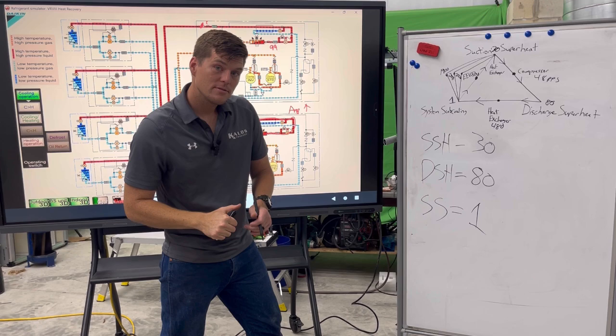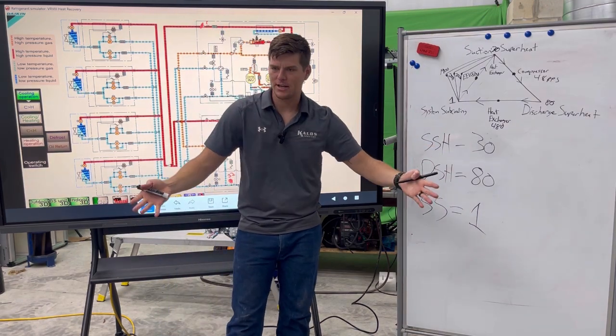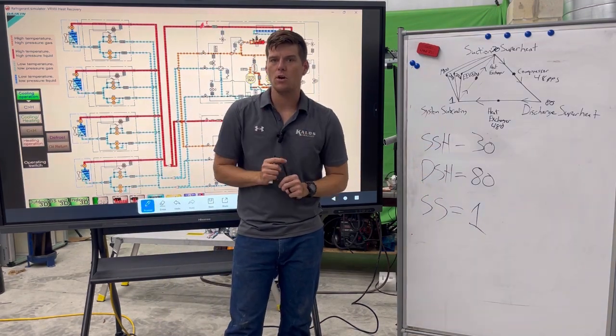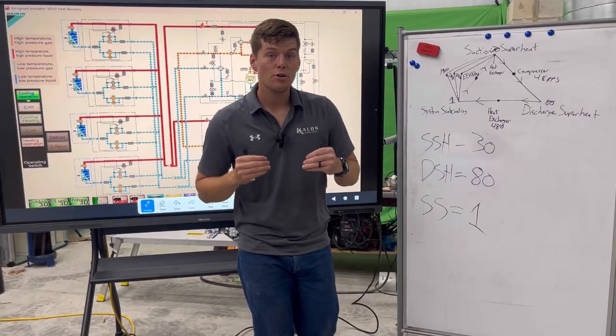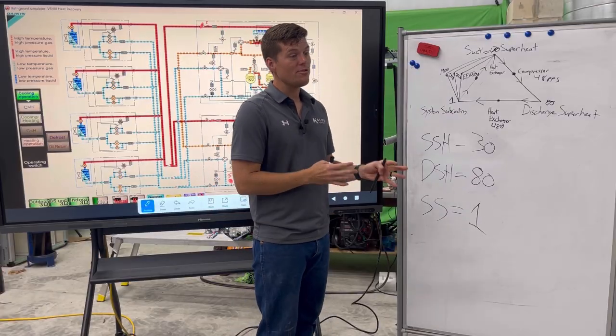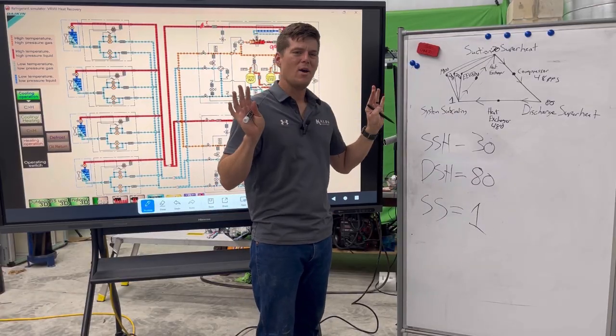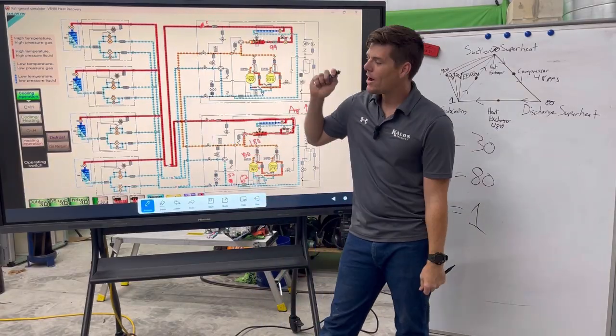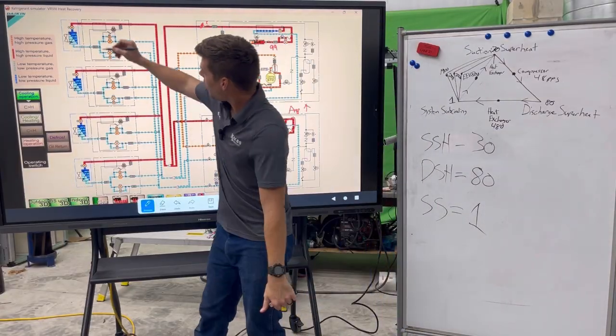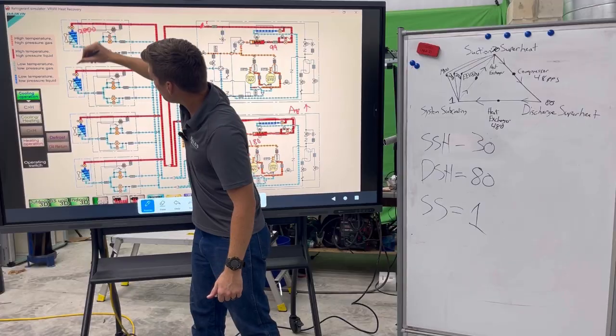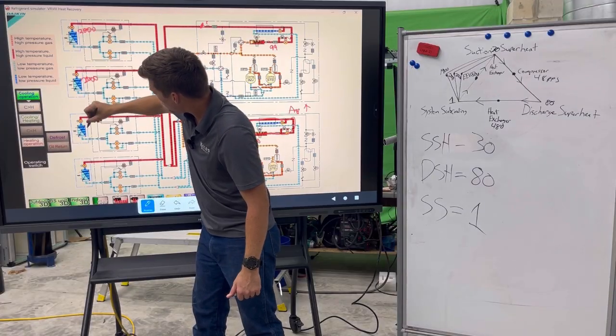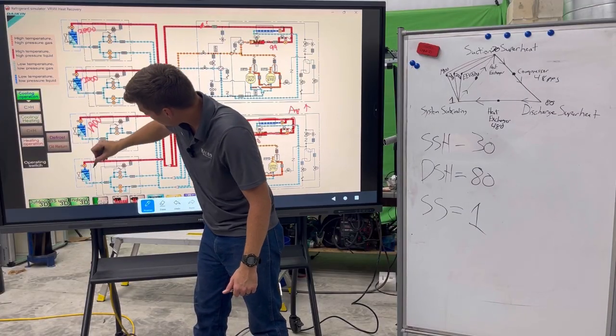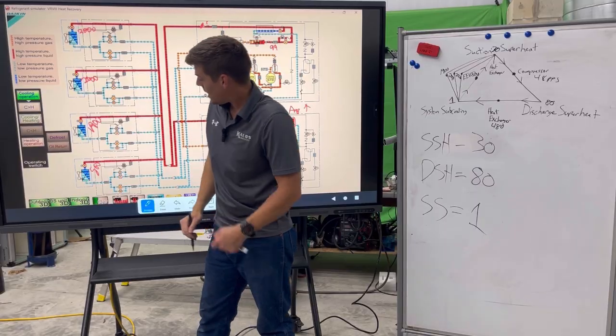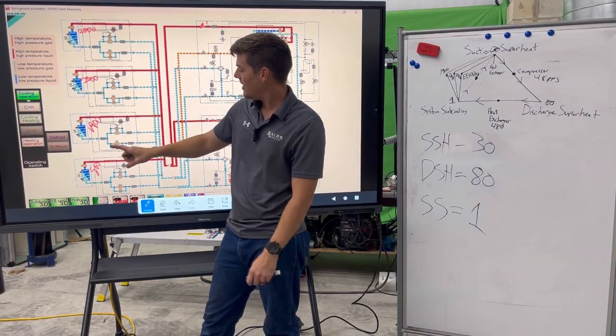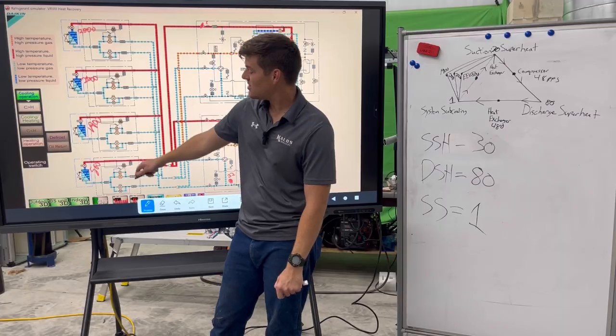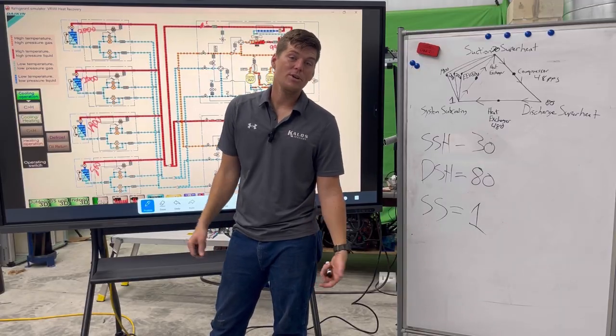Well, that's not good. Remember, the whole purpose of an electronic expansion valve is to do one thing and one thing only, and that is to meter refrigerant. Well, if it's not metering refrigerant, how do you know that it's not metering refrigerant, Roman? Well, I know it's not metering refrigerant because all my indoor valve pulses are wide open. Now, they're not all wide open, this one's at 800. And it's like, wait a minute, this is a small tonnage unit. Maybe this is a half-ton unit in a closet somewhere. Well, yeah, it's at 800 pulses.